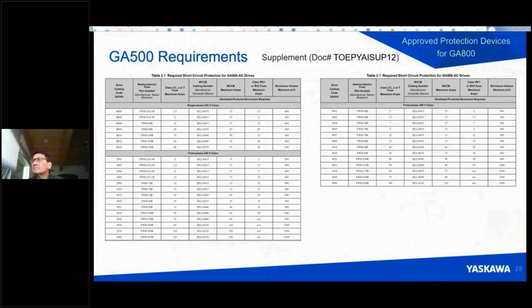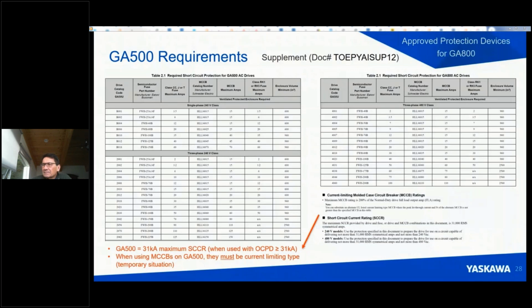And then we also have a similar document for the GA500. It has slightly different limitations. First of all, the GA500 is limited to 31,000 amps maximum SCCR. So that's an important difference. And then as far as the MCCB style that needs to be used, it's actually very specific right now in the case of the GA500: the specific type of MCCB that needs to be used at this point in time is a current limiting type. So please read the notes on that. We always suggest a current limiting type of circuit breaker, but in the case of the GA500, presently, that's what it needs to be. But we are doing additional testing to hopefully remove that restriction in the near future.